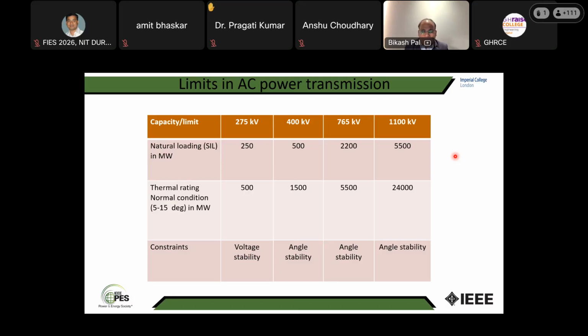And as we know, if there is no net var flow through a transmission conductor, there is no voltage difference created. That's why the voltage profile remains flat. But the receiving end voltage phase angle will differ from the sending end voltage phase angle. So that is called surge impedance loading, but it's very rare that one can load this. Now, what is the other thing in the second row? Thermal rating or normal condition.